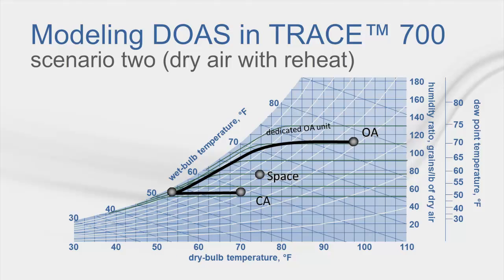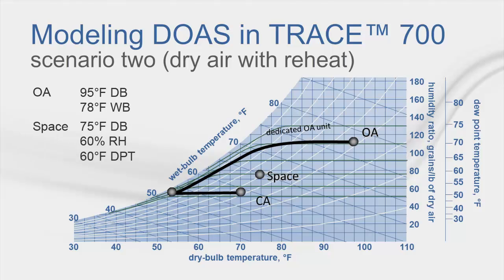Examining the psych chart on that hot and humid summer day at 95°F dry bulb, 78°F wet bulb outside, the DOA dehumidifies the outdoor air and then reheats it to approximately space-neutral temperature. The resulting dew point of the conditioned air is drier than the space, which means the DOA is removing part or all of the space latent load.